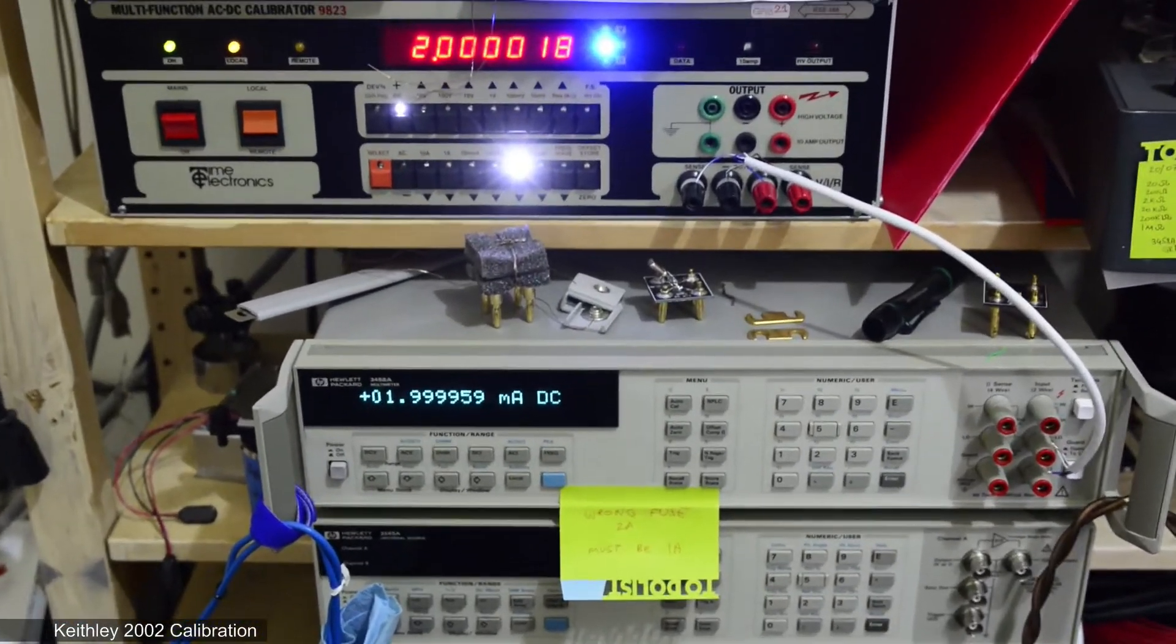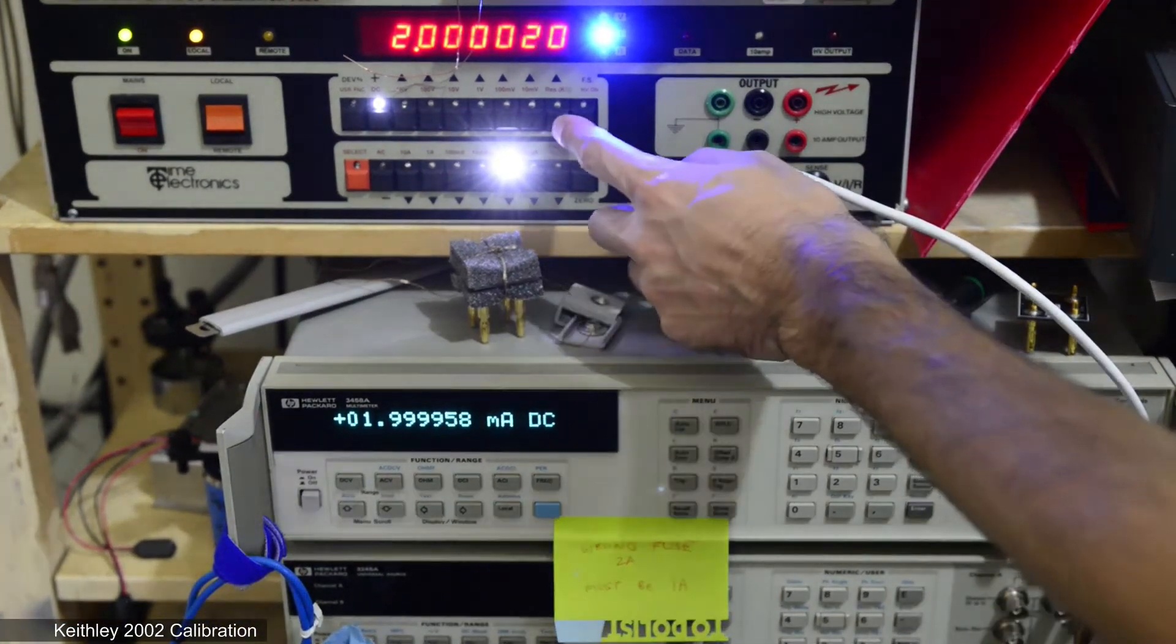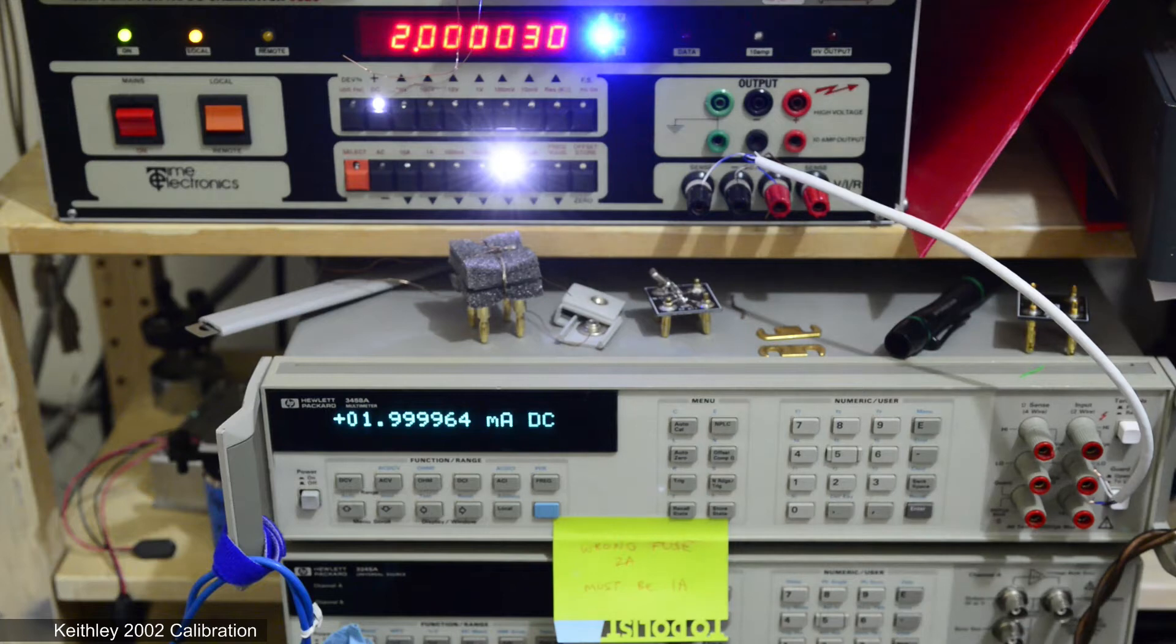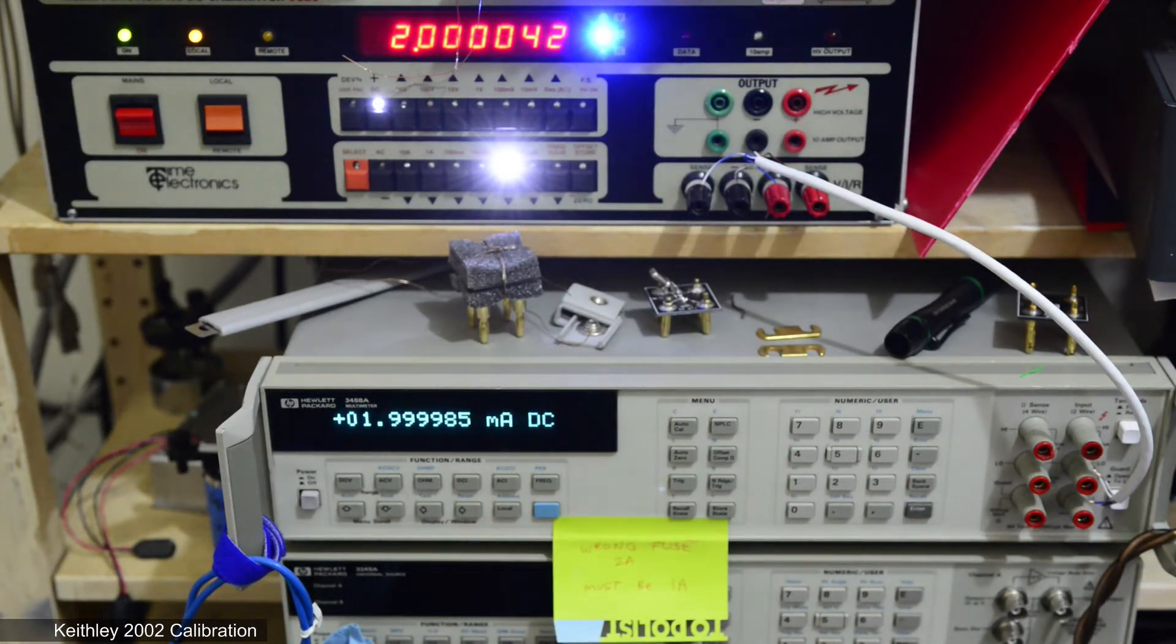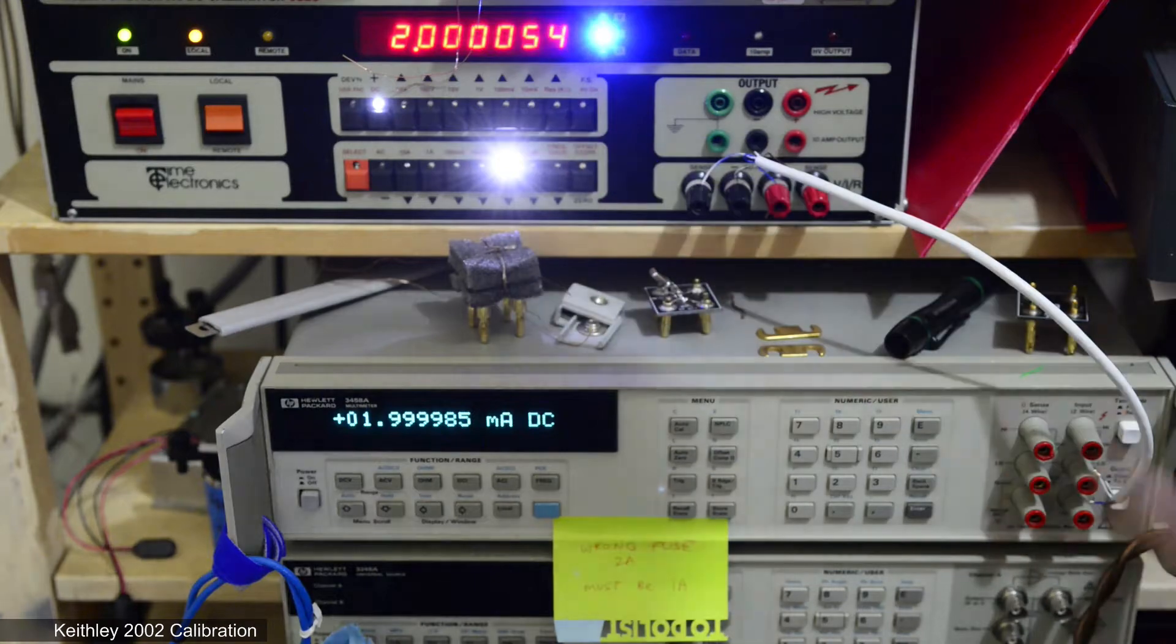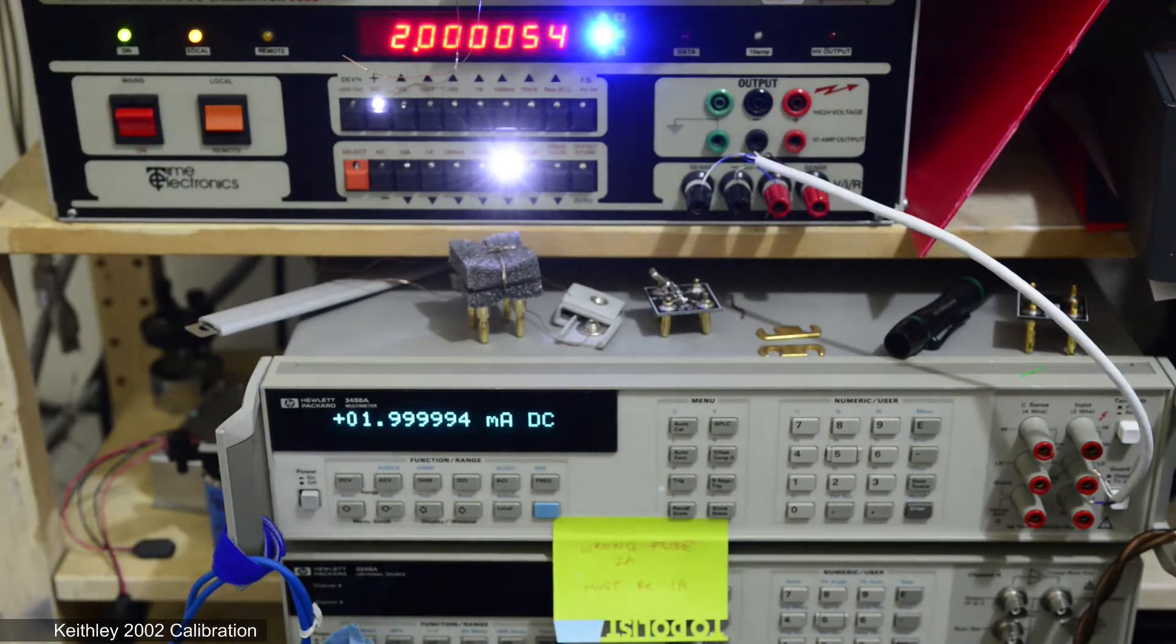User calibration procedure for Keithley 2002 multimeters requires 200 microamps, 2 milliamps, 20 milliamps, 200 milliamps and 2 amps.